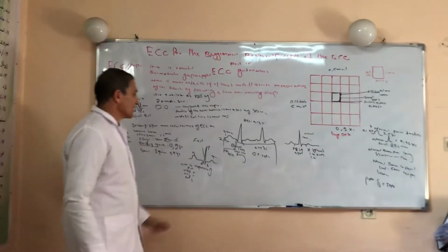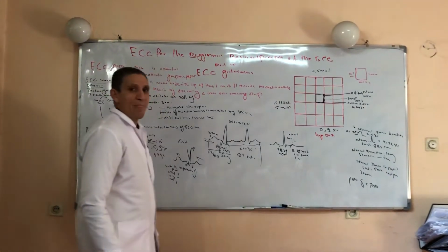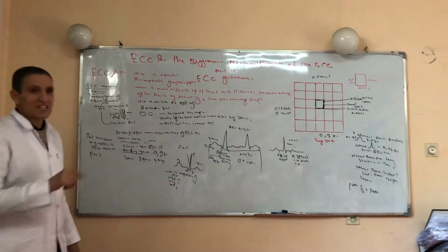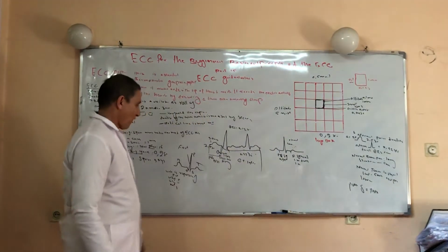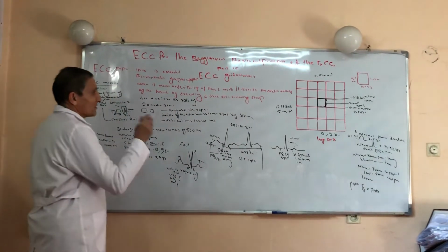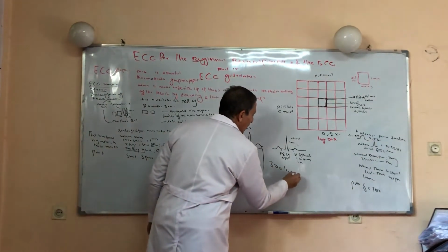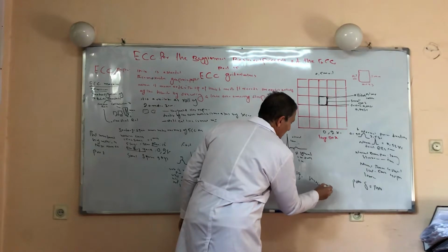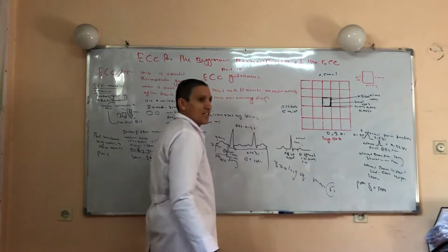What does it mean? Constant rate means that 300 large squares of the ECG paper move under the needle of the ECG machine in 60 seconds. The standardization of the ECG machine is characterized by 2 things. The first thing, when 300 large squares or boxes move under the needle within 60 seconds. So 60 seconds equals 300, or 300 equals 60 seconds, or vice versa.